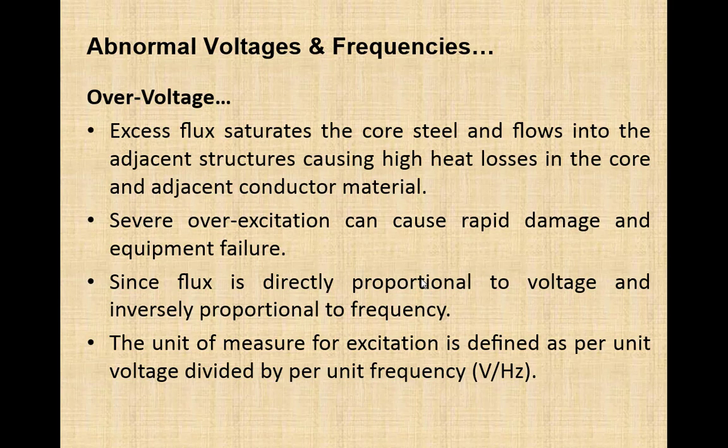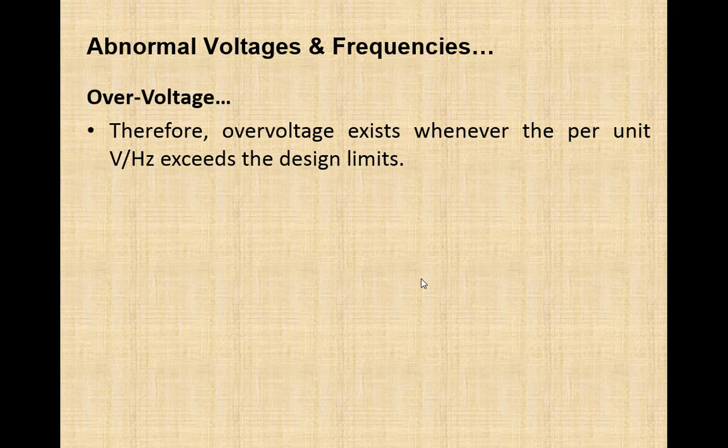So instead of just discussing this overexcitation concept in view of voltages, we will have to consider frequency as well. This overexcitation may result in heating of the core and metallic material around that core, and that is due to voltage as well as frequency. Therefore, overexcitation exists whenever the per unit volts per hertz, the voltage to frequency ratio, exceeds the design limits. So it means our overvoltage condition is discussed by keeping in view the frequency as well.